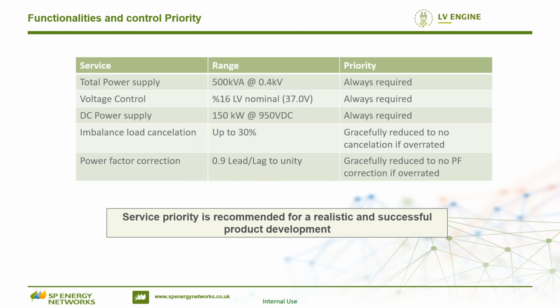So one of the things I was going to share with you is the service priority. When you design a power electronic unit, what we have here is a 500 kVA unit connecting at a nominal voltage of 400 volts. So the voltage control we can provide is 16% boost or buck, meaning the voltage we're getting at the LV terminal can be increased or decreased by 16%, which is 37 volts for each phase. And then the DC power of 150 kilowatts at 950 volt DC. So the imbalance load can be cancelled up to 30%, and the power factor correction 0.9 lead or lag to unity.